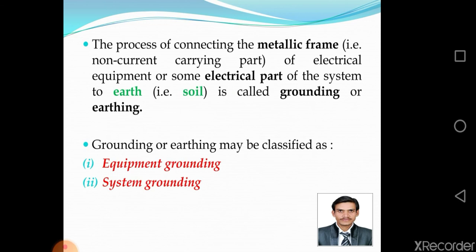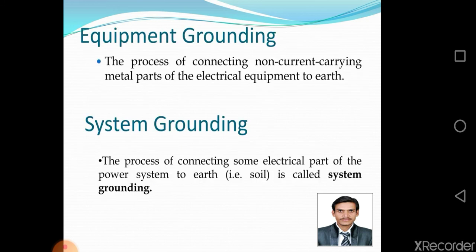The process of connecting the metallic frame of electrical equipment or some electrical part of the system to earth is called grounding, or it is also known as earthing. It means earthing and grounding is same. Grounding or earthing may be classified as equipment grounding and system grounding. Equipment grounding. The process of connecting non-current carrying metal parts of the electrical equipment to earth. System grounding. The process of connecting some electrical part of the power system to earth is called system grounding.